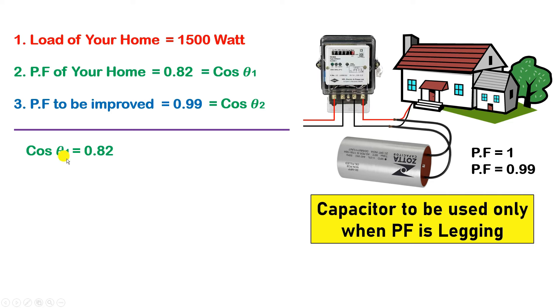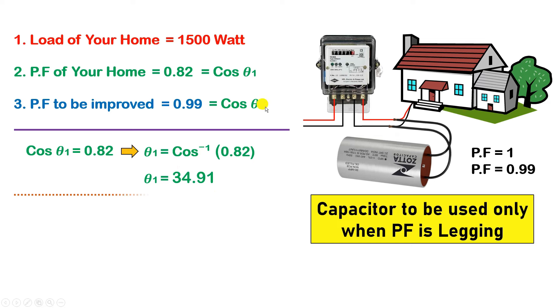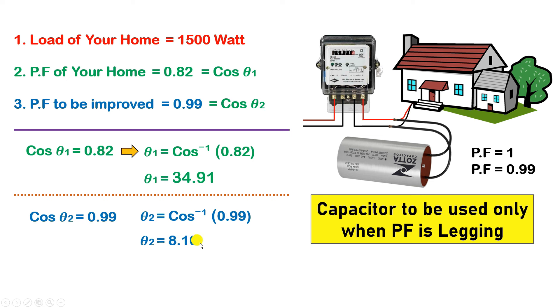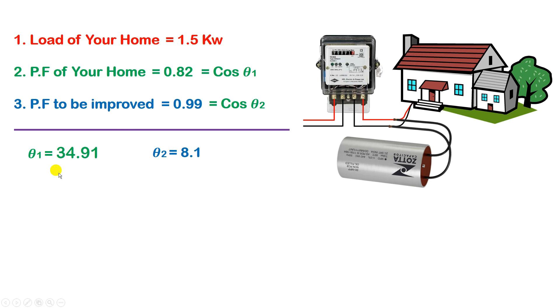To find theta 1: cos theta 1 = 0.82, so theta 1 = cos⁻¹(0.82) = 34.91 degrees. Similarly, cos theta 2 = 0.99, so theta 2 = 8.10 degrees. Now to find the required capacitor value in kVAR, we use the formula: kVAR = kW × (tan theta 1 − tan theta 2).